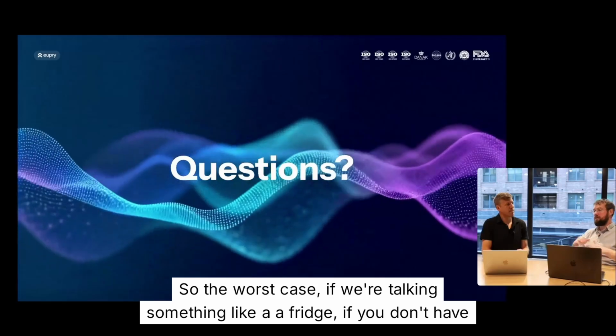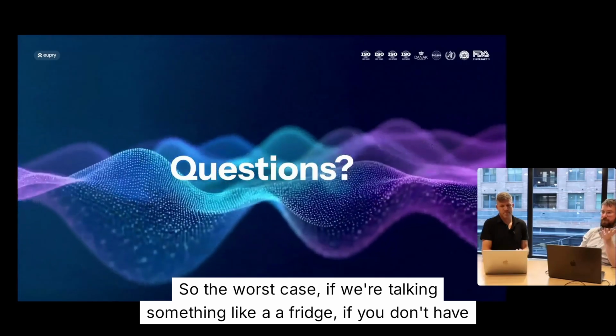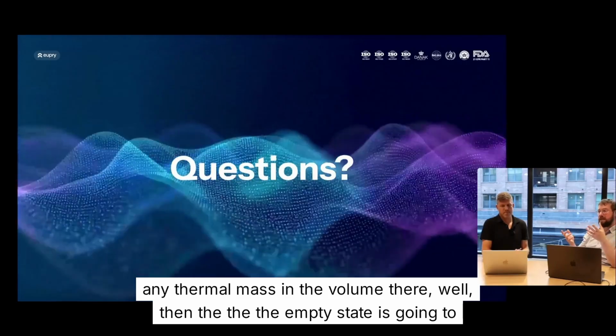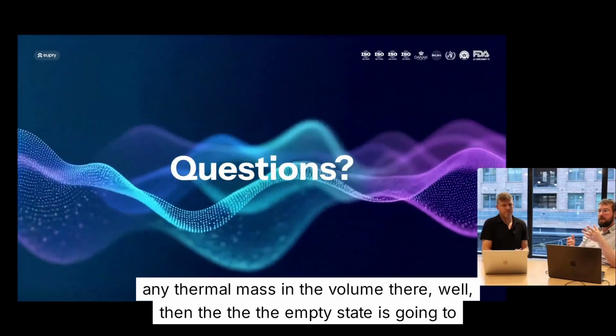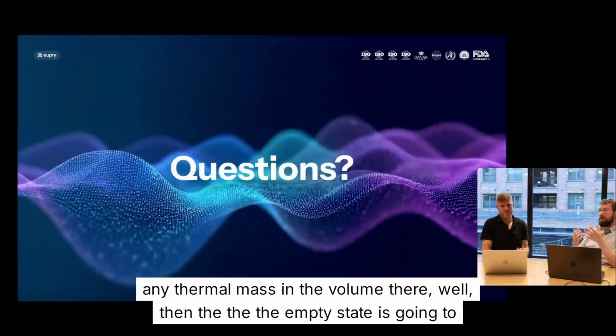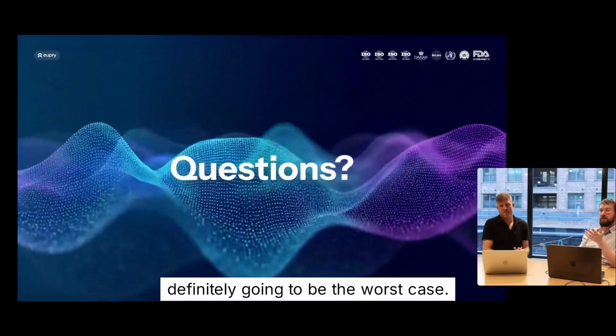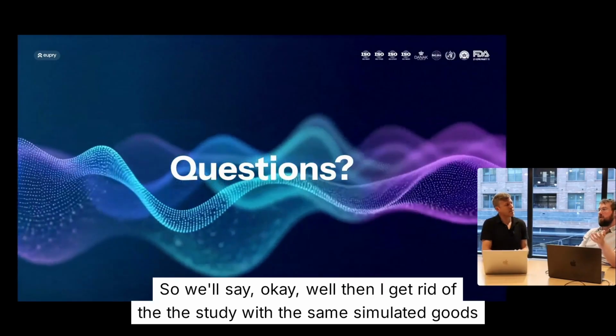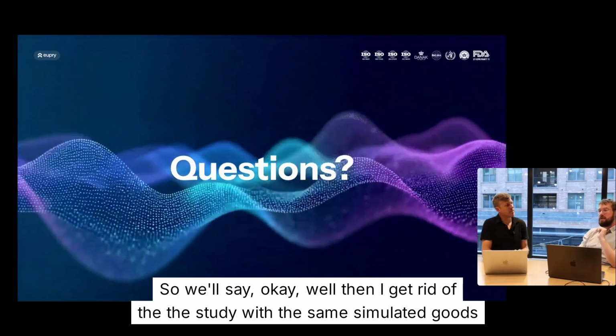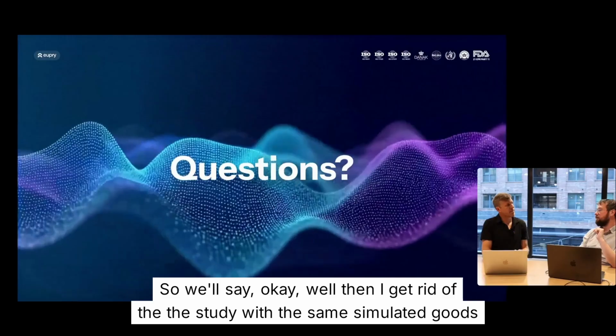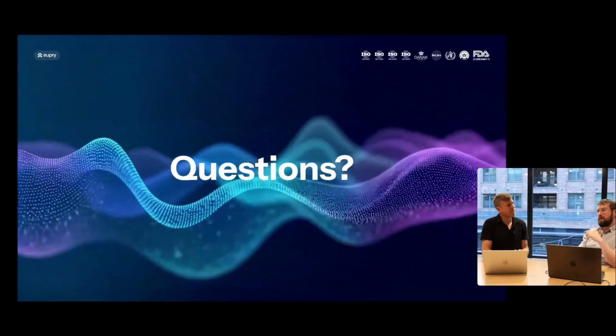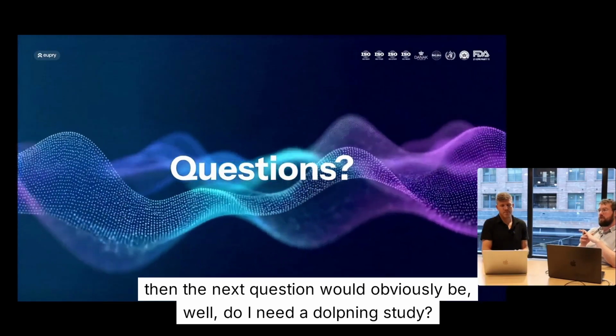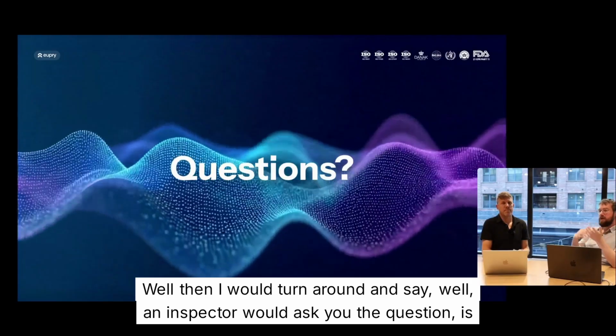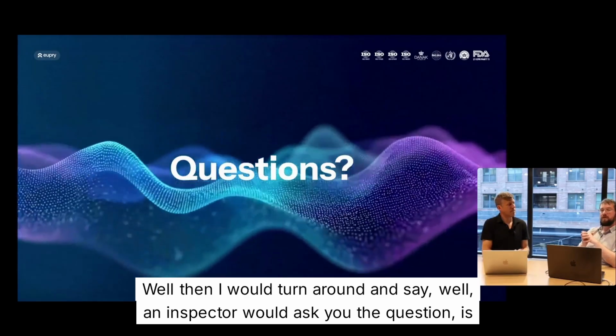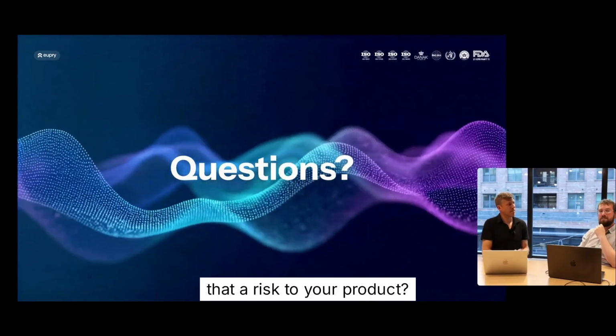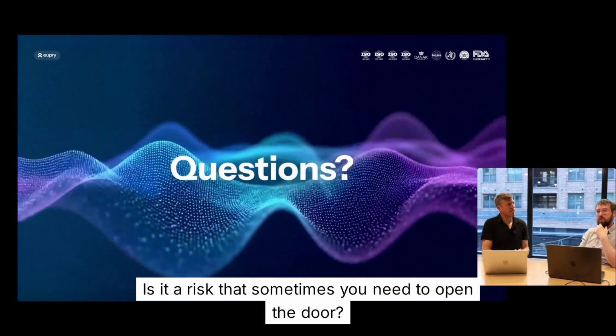So the worst case, if we're talking something like a fridge, if you don't have any thermal mass in the volume there, well, then the empty state is definitely going to be the worst case. So we'll say, okay, well then I get rid of the study with the simulated goods in there. Then the next question would obviously be, well, do I need a door opening study as well? Well, then I would turn around and say, well, an inspector would ask you the question, is that a risk to your product?